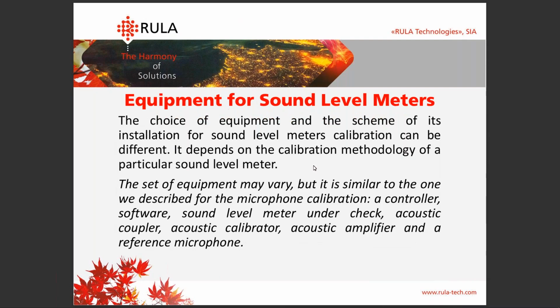Now, about the equipment that you're going to need for sound level meters. Here is a slightly more complicated situation. You don't see any scheme here because there's a range of such devices, and with every kind of device, you're going to have to refer to the related standard. In this standard, there will be steps or methods described. Depending on these methods, which are, by the way, all implemented in our software, the set is going to be different. There are about 4 possible sets, hardware configurations that you could have to collect for performing the calibration of sound level meters.